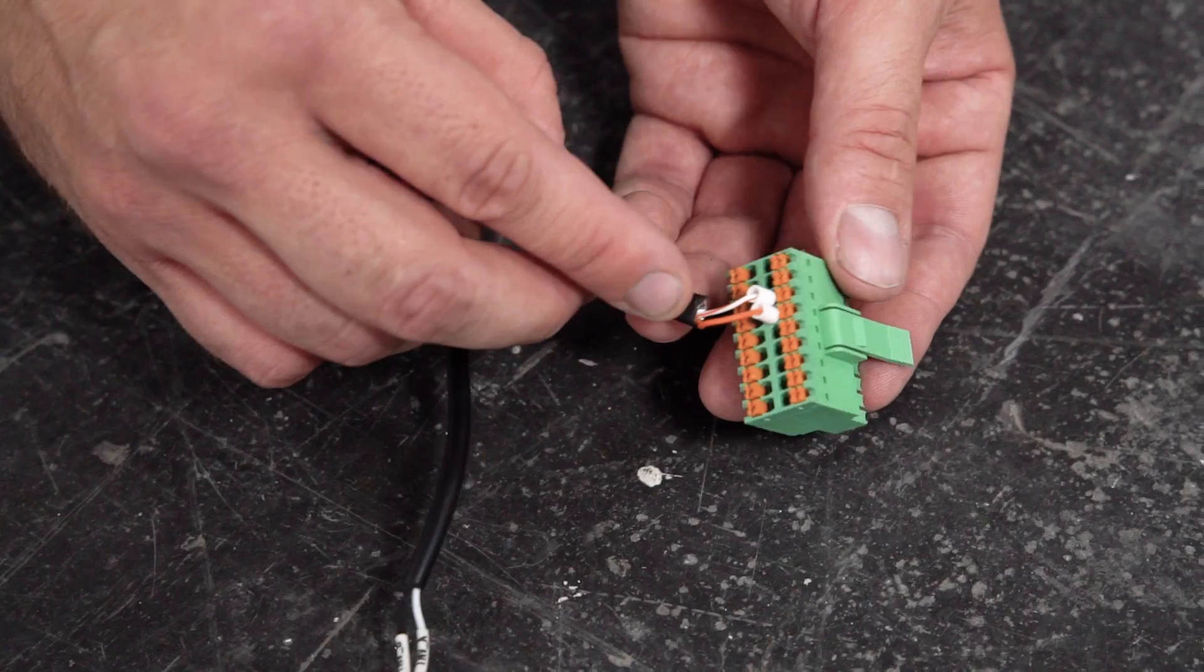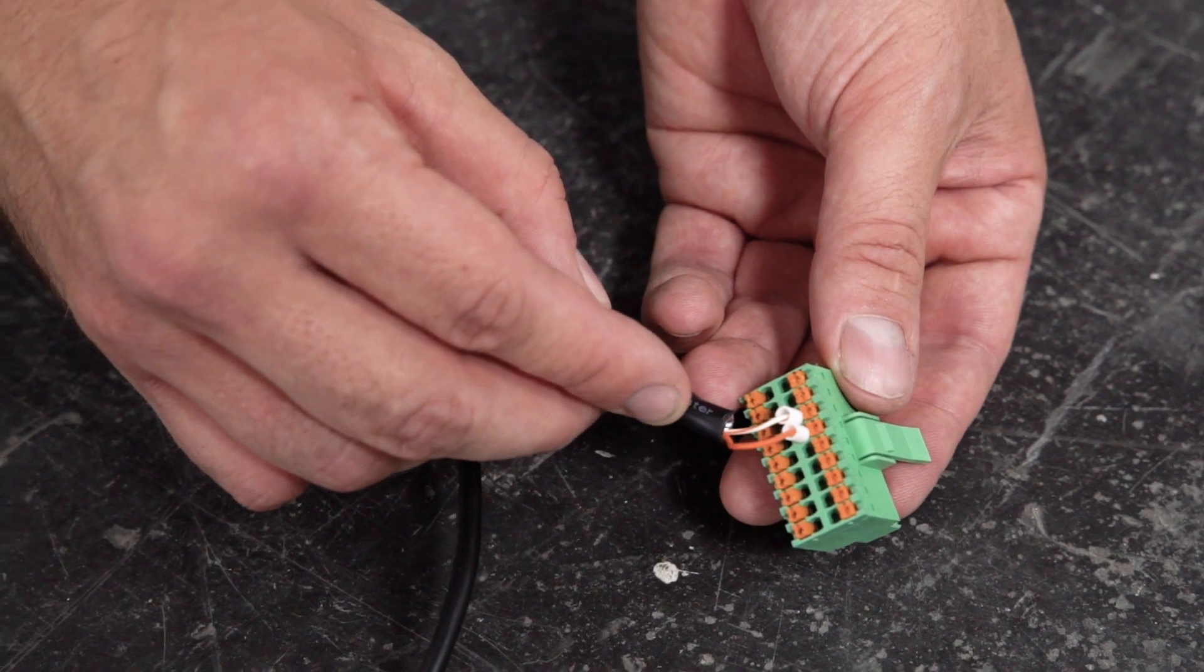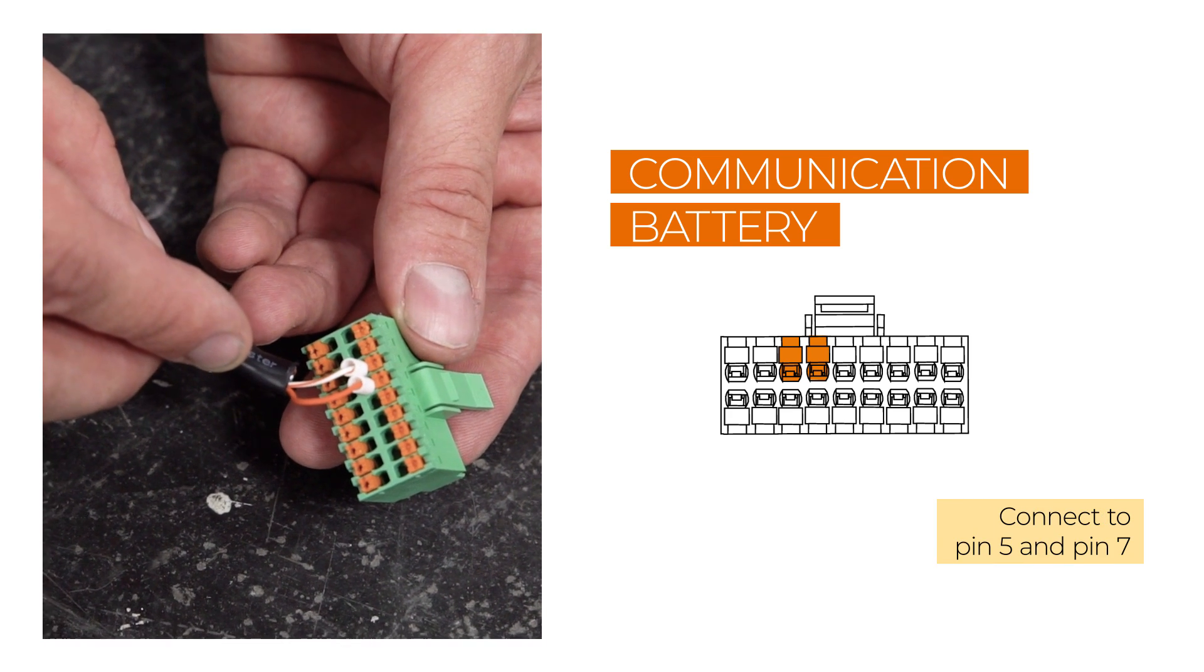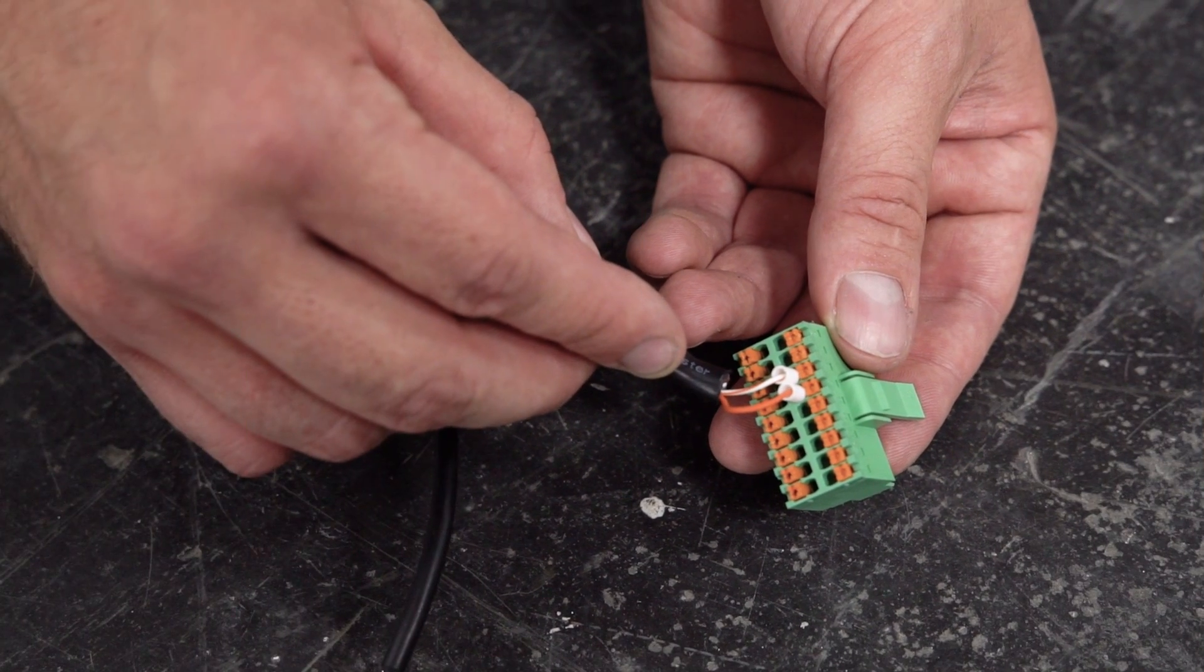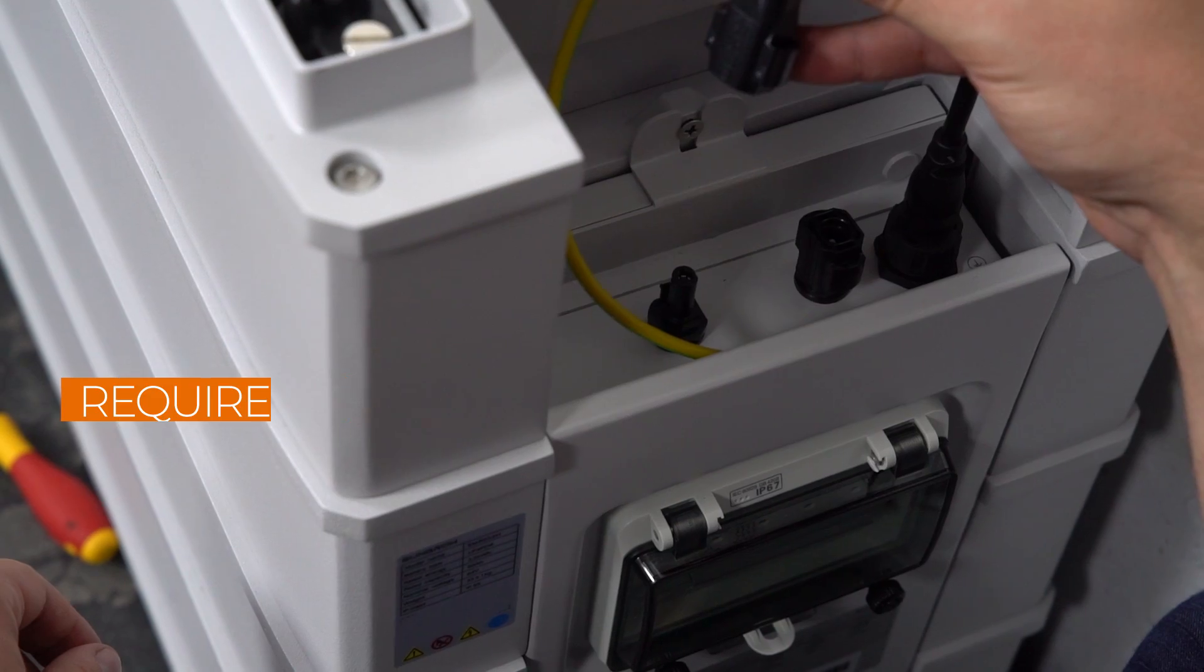Connect the white orange cable to pin 5 and the orange cable to pin 7. Connect the battery power cables to the P minus and P plus port on the battery side.